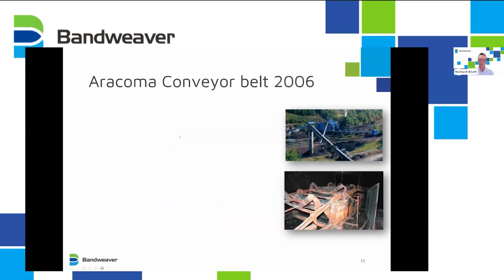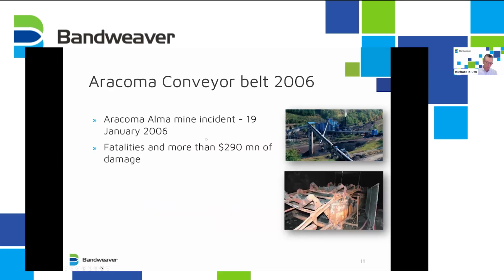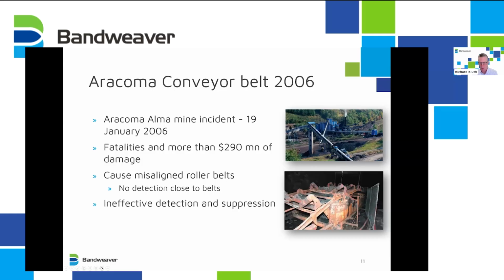Looking at a conveyor belt example, this is 2006, Aracoma Alma mine, the 19th of January, which is based in the US. This was a horrendous fire with multiple fatalities and more than $290 million of damage. The cause of the fire was misaligned roller belts, and so a build-up of friction, which started the fire. There was no detection close to the belts. As we'll see, the detection and suppression was ineffective.